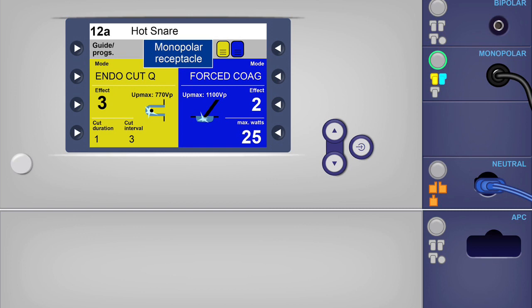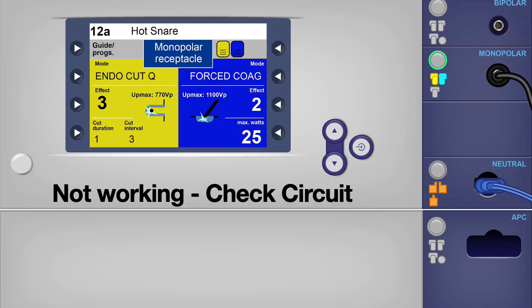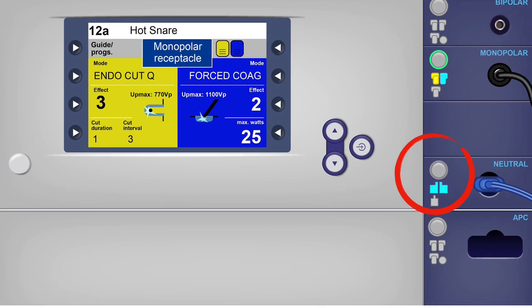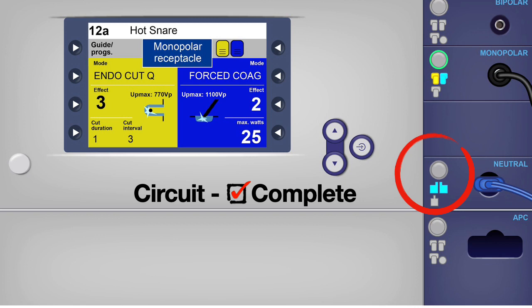But unfortunately you tried to cut, but nothing worked. And in that case, what you should do is you should check the circuit. And you would know when you look at the neutral electrode and you see those two orange foot pedal colors, that means the circuit is not right. You may have to recheck the whole circuit, whether everything is plugged in right. And sometimes the assistant forgets to plug the electrode into the snare handle. So that's all been checked, and now it looks like the circuit is complete, and we should be able to go ahead and cut that polyp.